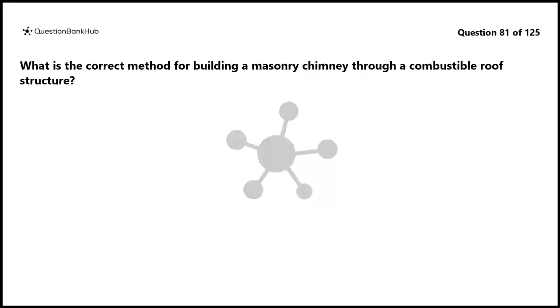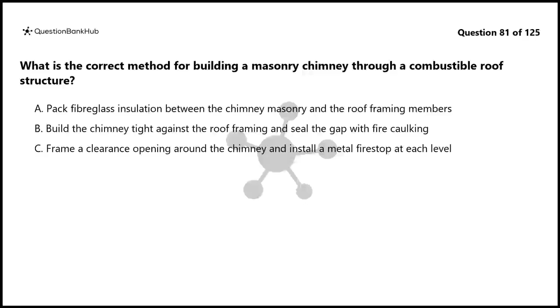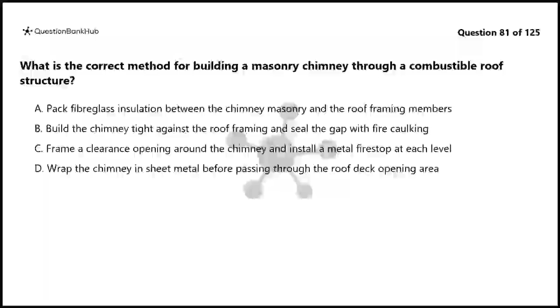Question 81. What is the correct method for building a masonry chimney through a combustible roof structure? A. Pack fiberglass insulation between the chimney masonry and the roof framing members. B. Build the chimney tight against the roof framing and seal the gap with fire caulking. C. Frame a clearance opening around the chimney and install a metal fire stop at each level. D. Wrap the chimney in sheet metal before passing through the roof deck opening area.